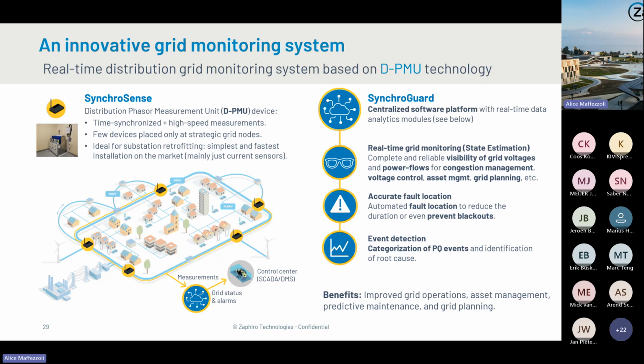I will go through the technology in a moment, but basically it provides very fast information and high quality measurement, done with time synchronization. Thanks to this, we don't need to install PMUs throughout the whole grid. We just need to select some critical points of the grid to have full observability of the complete grid.